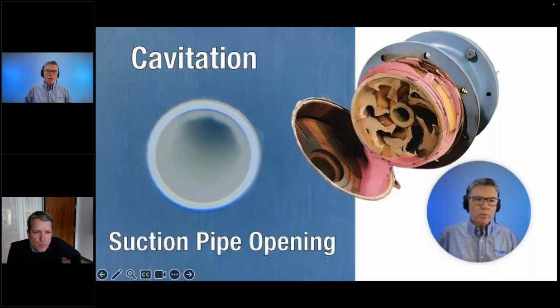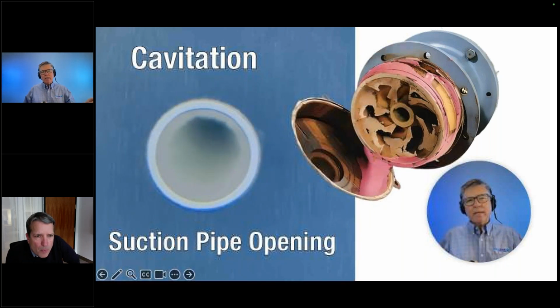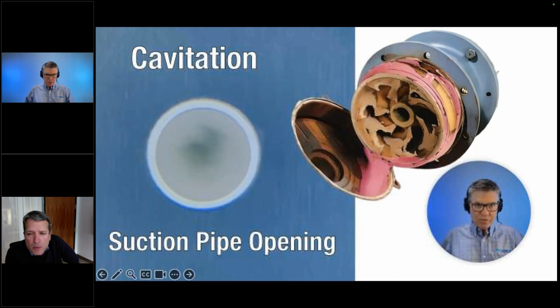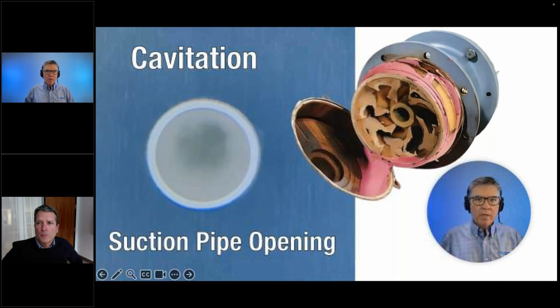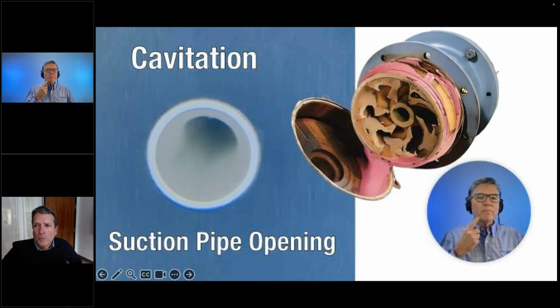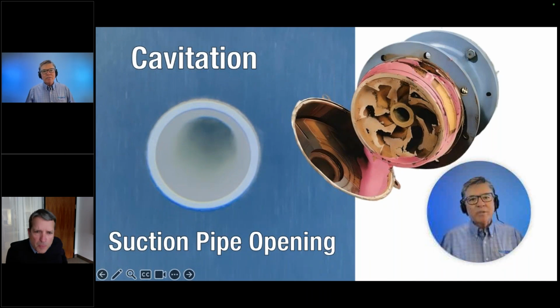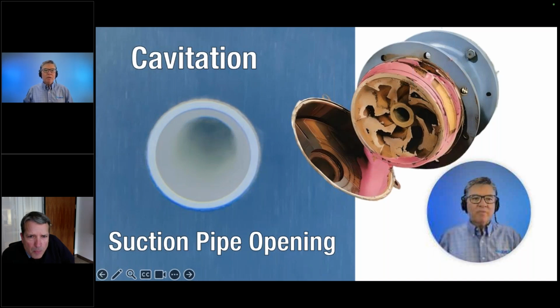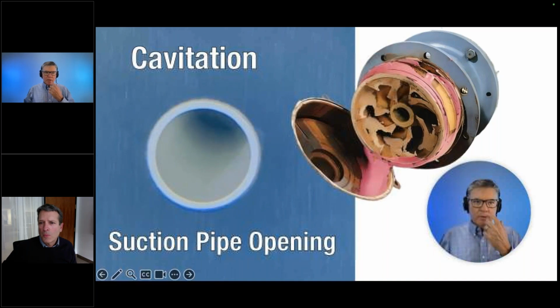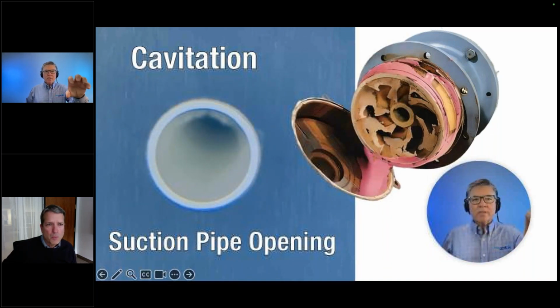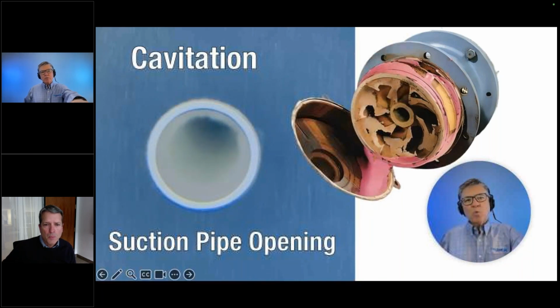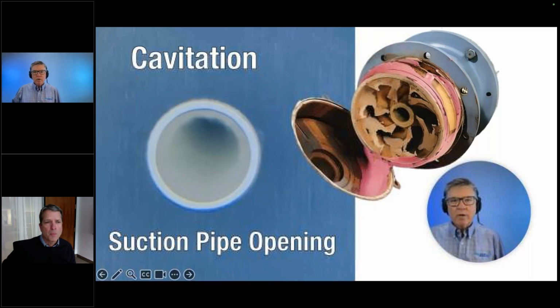Now, in this case, this was done in the AquaStar lab, and this is 22 inches of 1.5 inch pipe, and then it goes to 6 and ultimately 10 inches of pipe. The only reason this demo was possible is because of that pump that I mentioned that I messed up with cavitation. We think this was when it happened. Because it was 10-inch pipe 20 feet away, it was able to keep up for, I don't know, a minute or so before it got to the pump and caused a problem. So again, I'll show this one more time. This is extremely noisy. You can't hear it, but this is what cavitation is, and it's vaporizing the water.